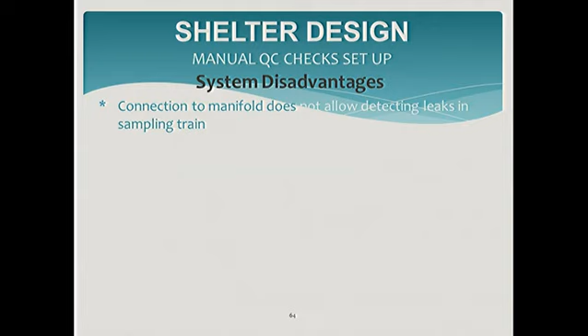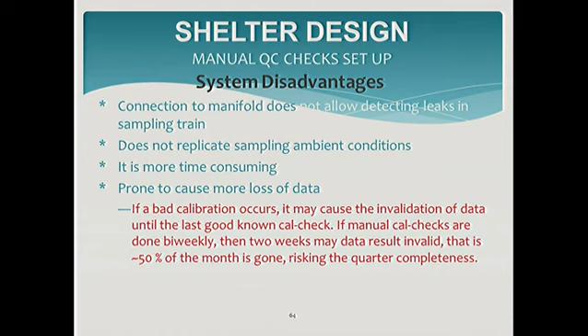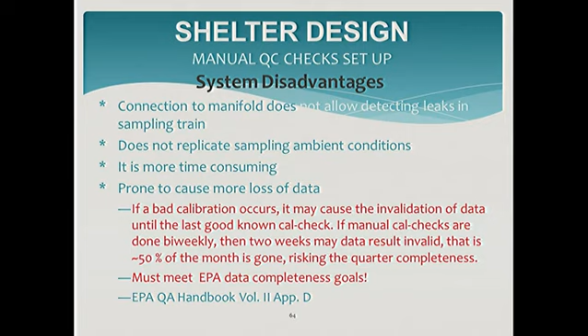This is the manual QC check setup disadvantages. Biweekly cal checks are minimal, and these are required. The techs are pretty good about keeping up with good calibration results, but there's always a potential that something will go wrong. When that happens, you end up invalidating a lot more data, and we've been talking about trying to preserve data completeness as much as possible. With the automated system, you'd probably invalidate a day to maybe no more than a week, so manual checks have a lot more potential for data invalidation issues.